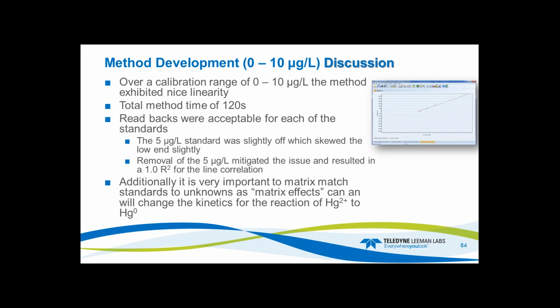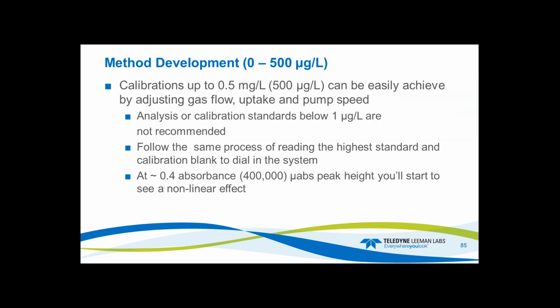So quick, it exhibited a nice linearity. Readbacks were acceptable. The 5 was slightly off, which skewed it. I removed it. It worked perfect. And again, matrix match. So here's the new calibration line down in the low end. Once I moved it, everything went right through the points. It was perfect. Here's the big one.